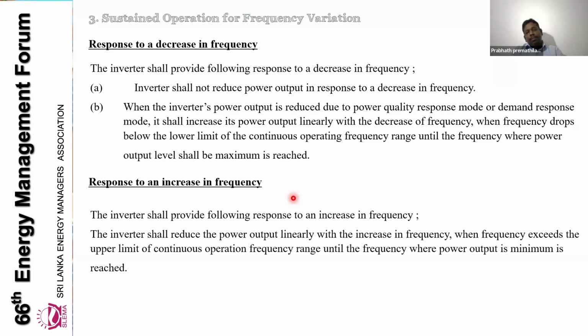And in the other way, when the frequency is increased, of course we have the active power capability, and we are reducing the power output linearly as the frequency increases, until it exceeds the upper limit of the continuous operation range, until the minimum power output is reached.